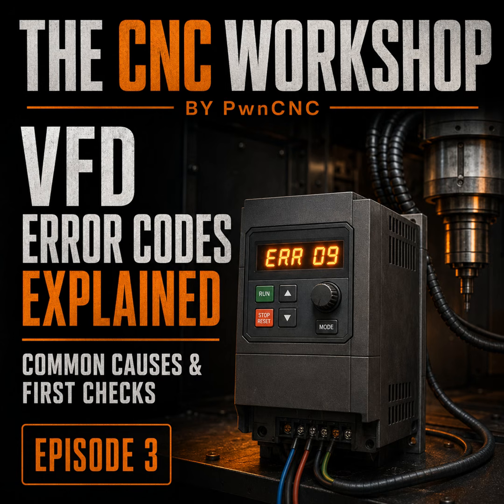So ERR31 is the one where we should be careful not to say, I must have pushed the cutter too hard. Exactly, especially if the error occurs during a light finishing operation or while the spindle is not meaningfully loaded. If the cut should require very little power and the VFD still reports a current detection fault, cutting parameters become a less convincing explanation. What observations should we write down? Note whether ERR31 appears immediately after starting, only after the spindle warms up, only while cutting, only while the machine moves, or during both loaded and unloaded operation. Those details help separate a thermal or internal fault from a movement-related cable issue or a cutting load problem.